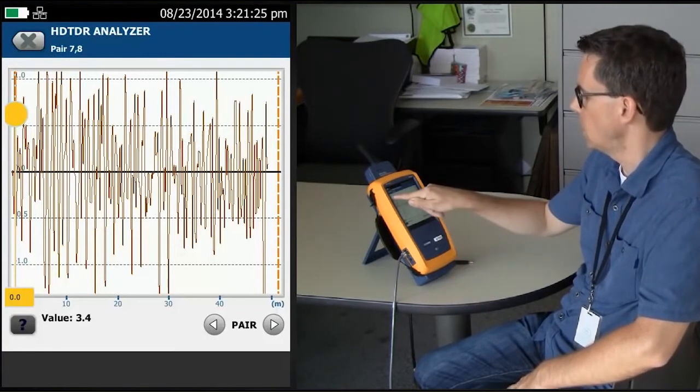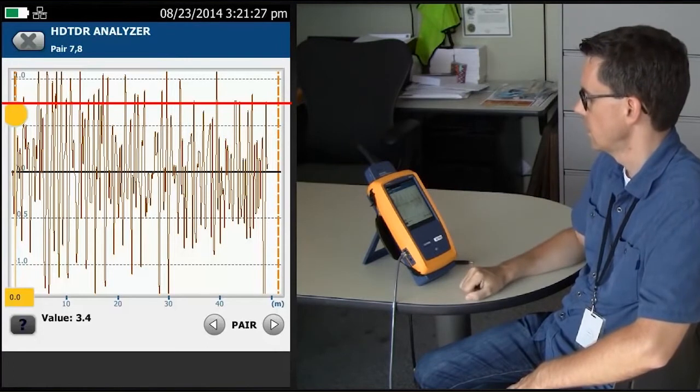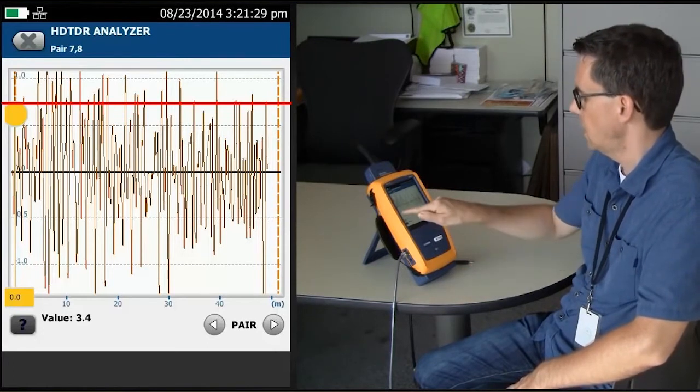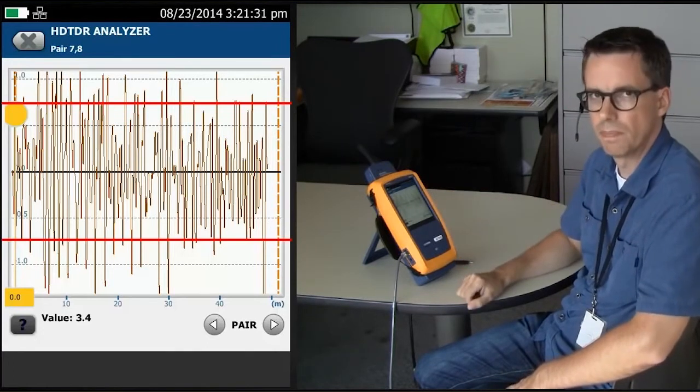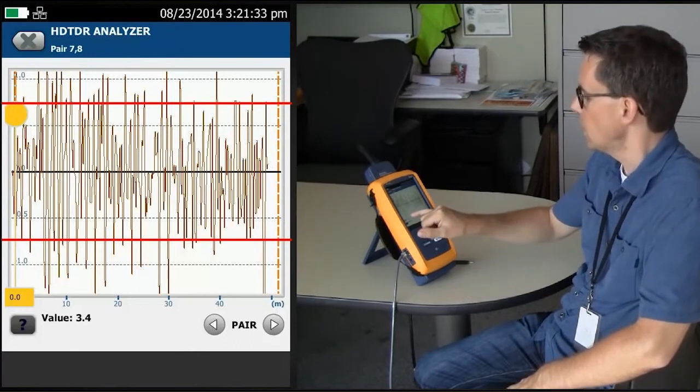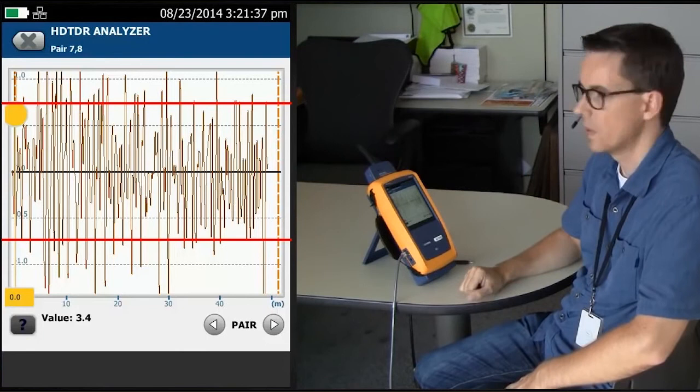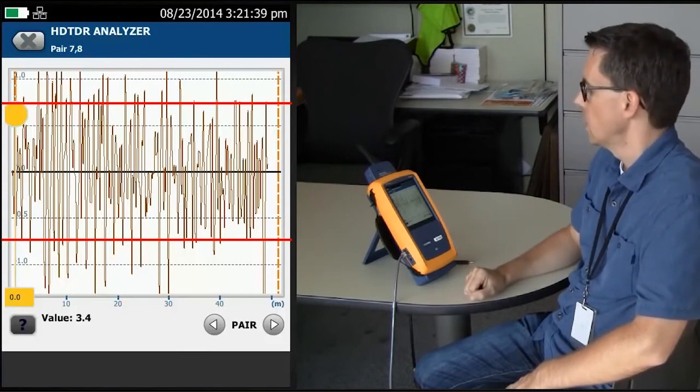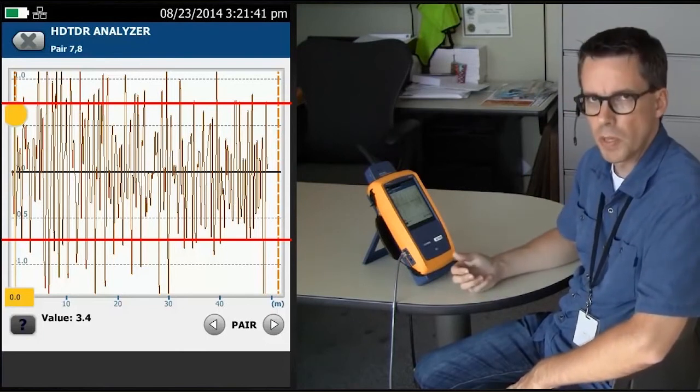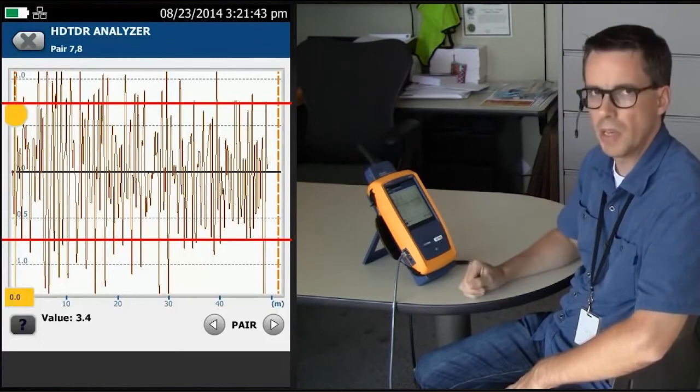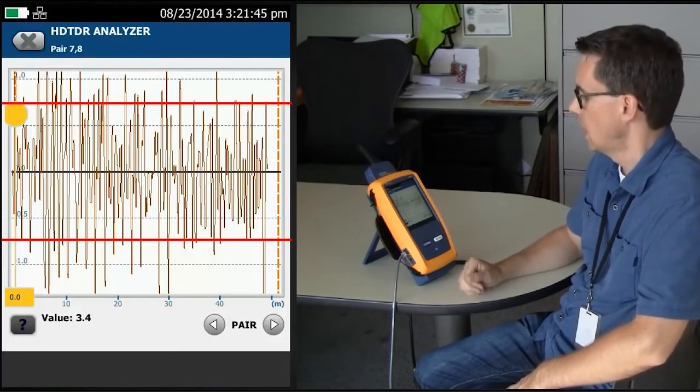Let's go ahead and put in 0.8 and minus 0.8 here. And what we can see is we have multiple events exceeding 0.8, our guide. So that confirms our suspicions that since it is happening in the cable, we have a cable issue.